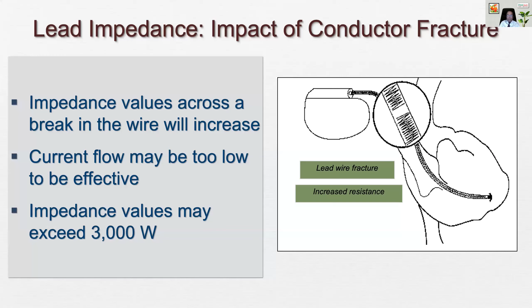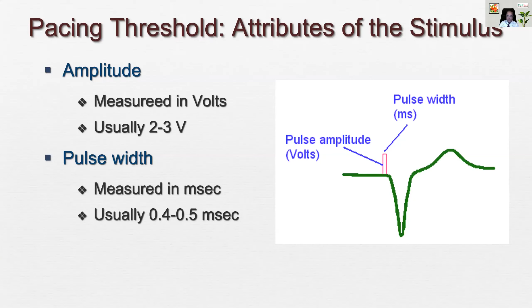Now coming to pacing threshold. Every pacemaker stimulus has two important attributes. One is the amplitude, which is measured in volts, and second is the pulse width, which is the duration of the pulse, measured in milliseconds, and usually 0.4 to 0.5 milliseconds is what is kept. As far as the amplitude is concerned, usually we keep around 2 to 3 volts. All modern pacemakers have what we call an auto capture threshold test. So the pacemaker can automatically perform tests to find the right amount of voltage to be programmed, which saves battery significantly.